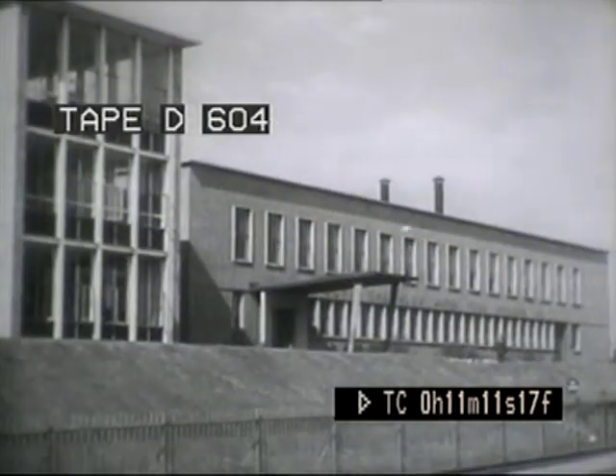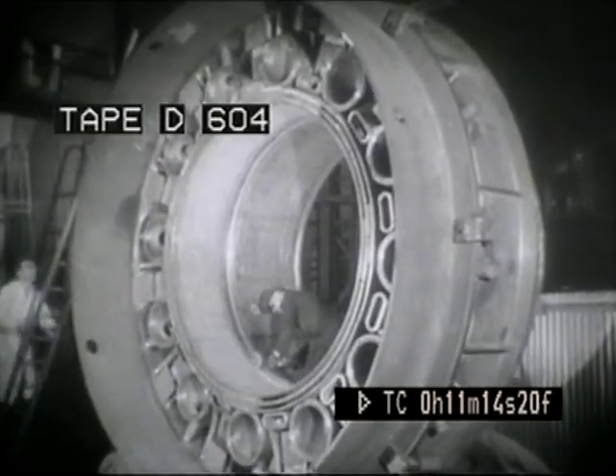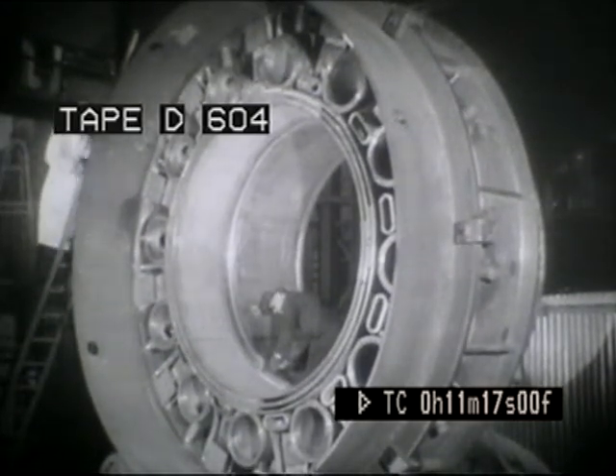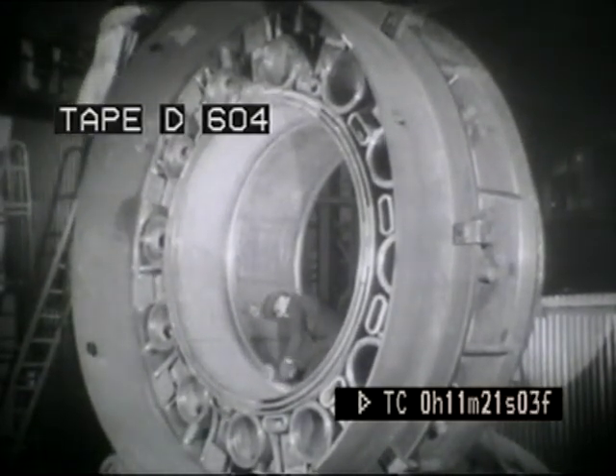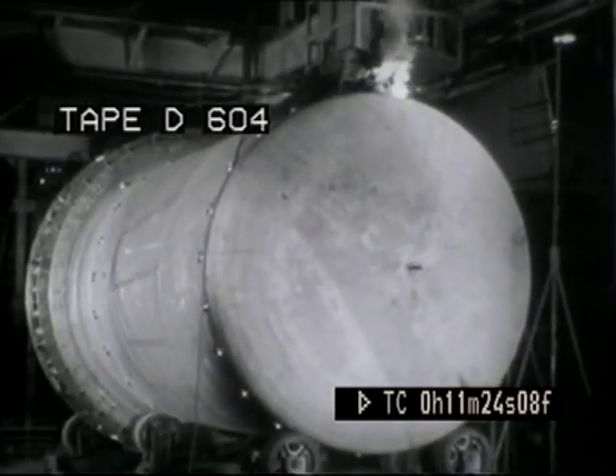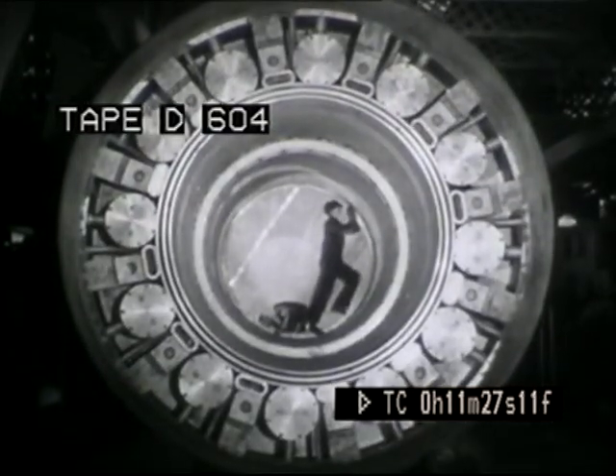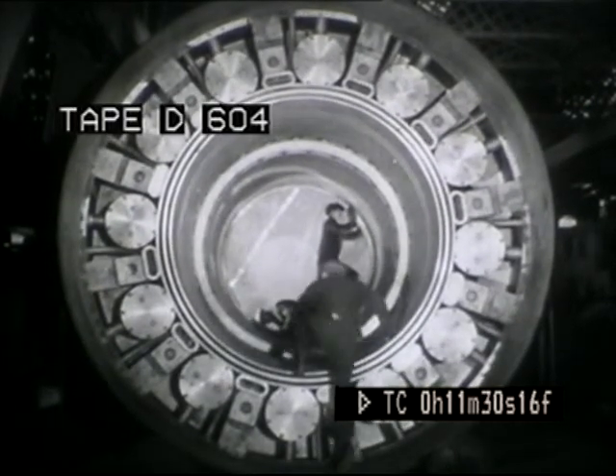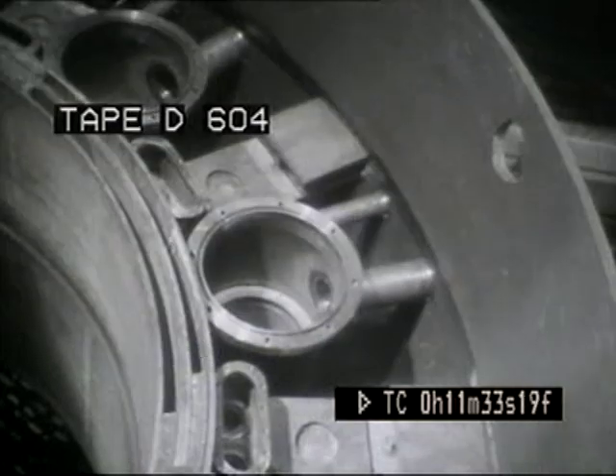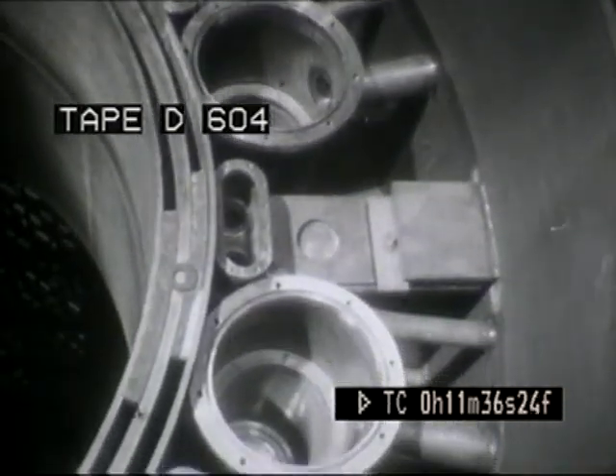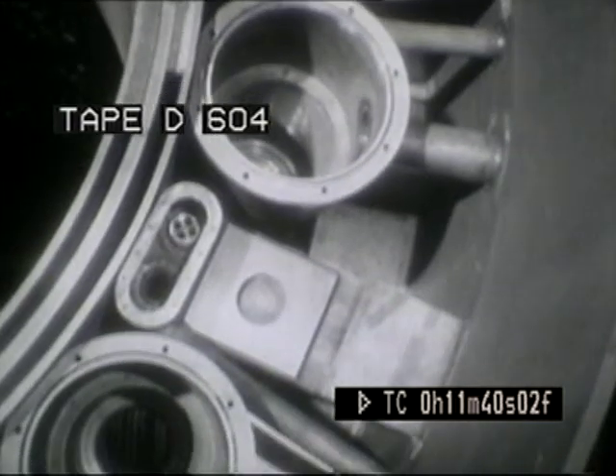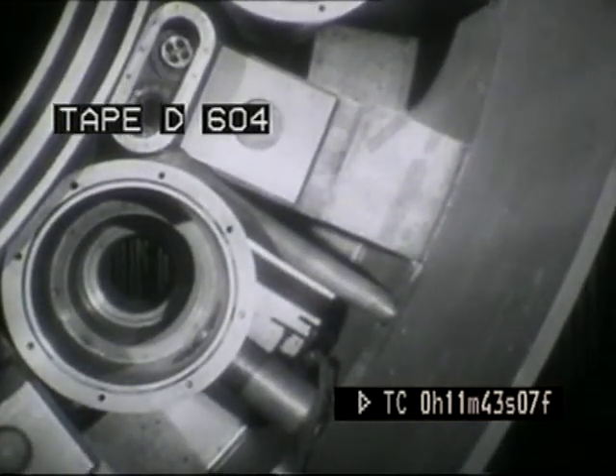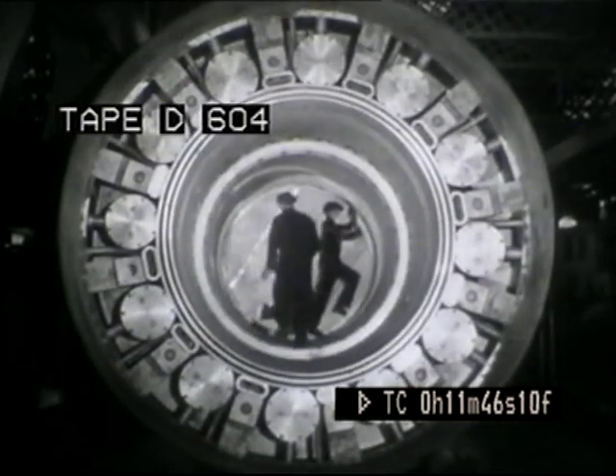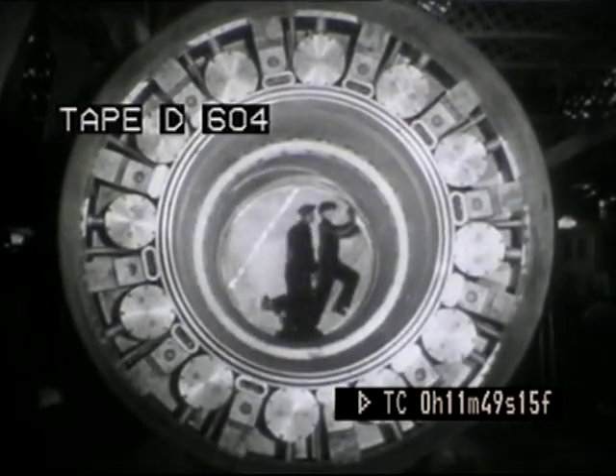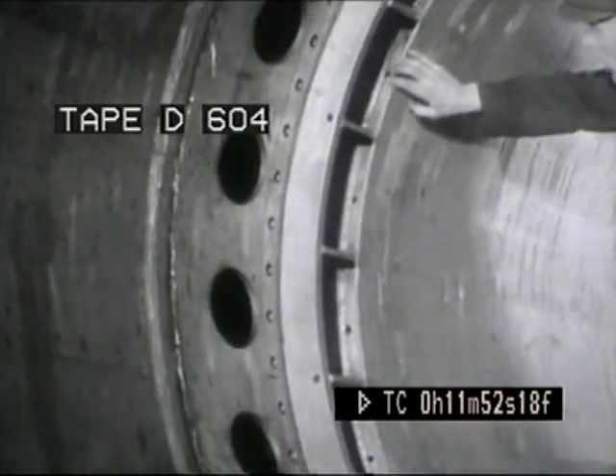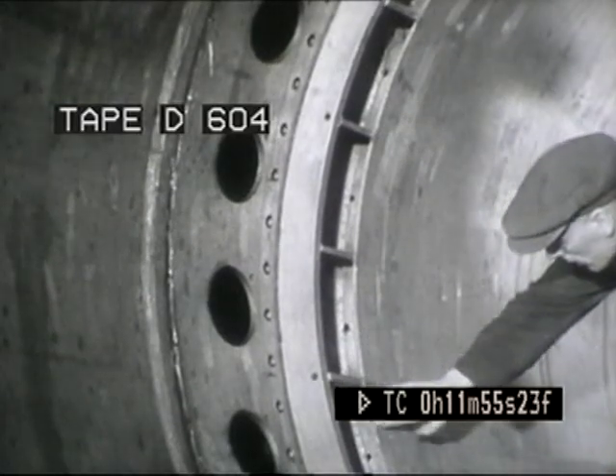At the contractor's works, the reactor vessel was under construction. It has been described as the most complicated stainless steel vessel ever produced in Britain and probably in the world. It consists of a double-walled outer vessel with a smaller inner skirt to contain the core of enriched fuel and the breeder blanket. Around the inner skirt will be the control rod mechanism. The tolerances called for in the fabrication of the vessel were quite outside normal practice, such as limits of 0.4% circularity and 0.2% alignment.